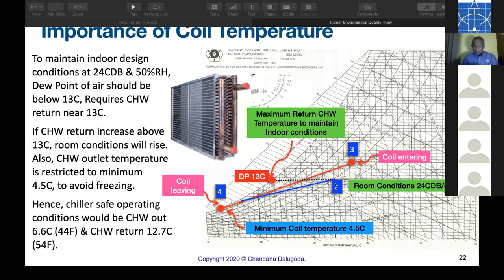Now, just have a look right here. This is your room temperature to maintain, that is 24 C dry bulb, 50 RH. The dew point temperature of air is 13 C. That is from psychrometry. So now you have a constraint on chiller supply and return water temperatures, or the air handling unit coil entering and leaving temperatures. That is, the air handling unit coil leaving temperature has to be maintained at 13, maybe 14.